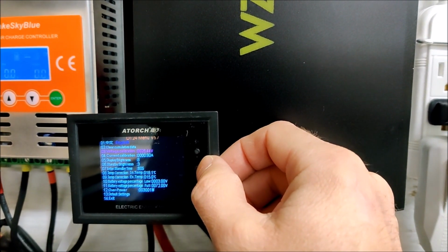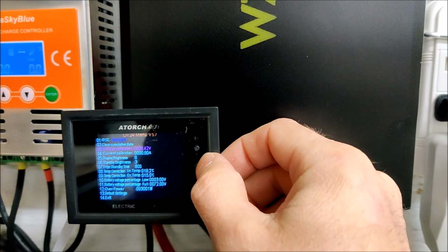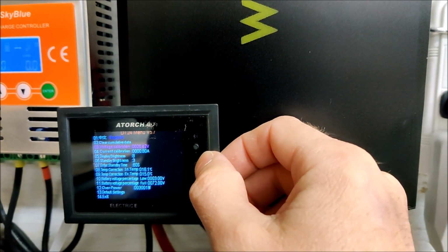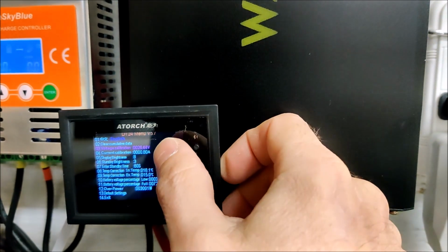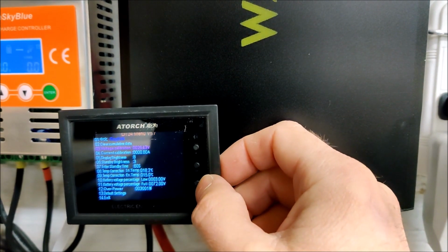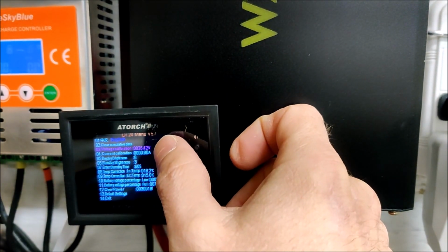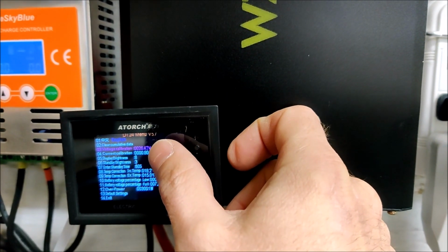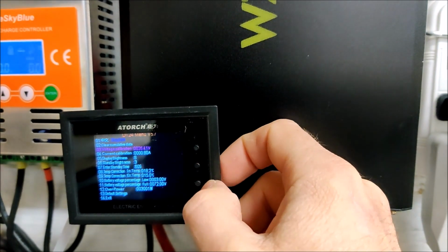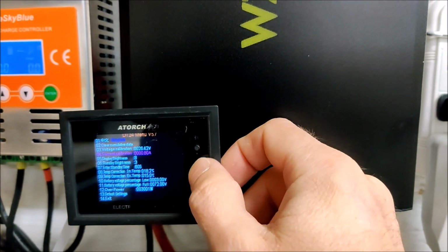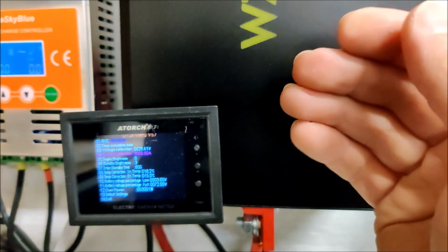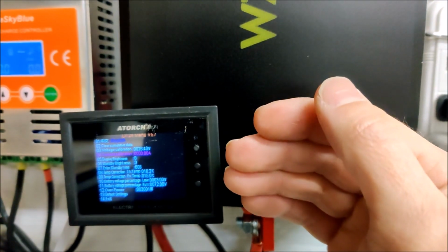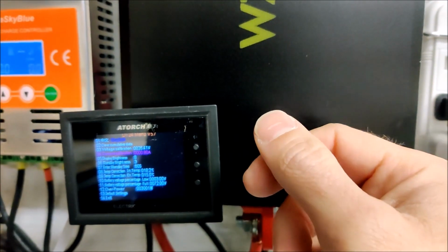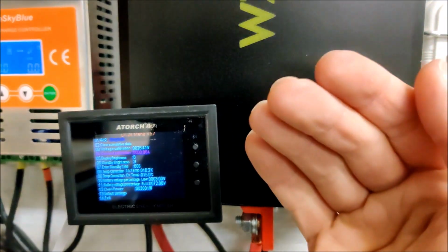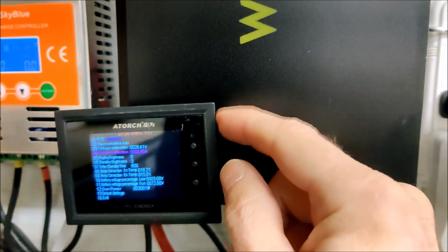Here you can actually put a voltage offset and a current offset on this screen. When I'm on voltage, if I hold the down button, it'll slowly drag that voltage down, and I'm actually putting in an offset. Same thing with current - if I move it to current and hold the down button, I can drag that current down with an offset. But that offset, I've learned the hard way, is only accurate at the current you're currently pulling.